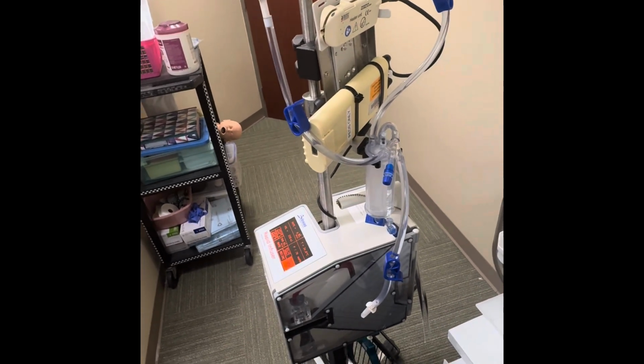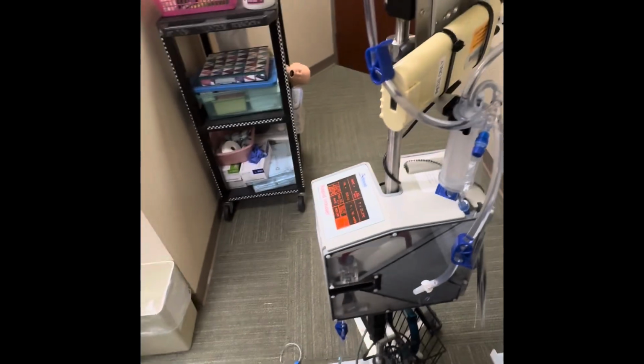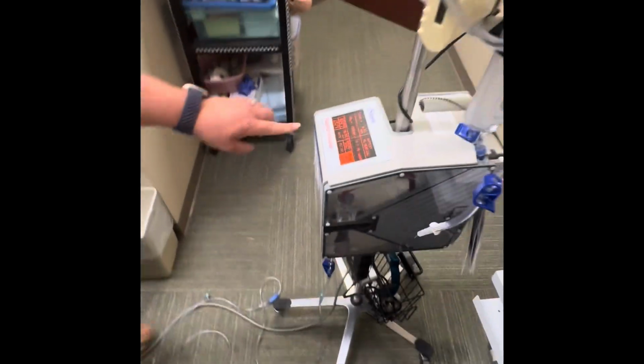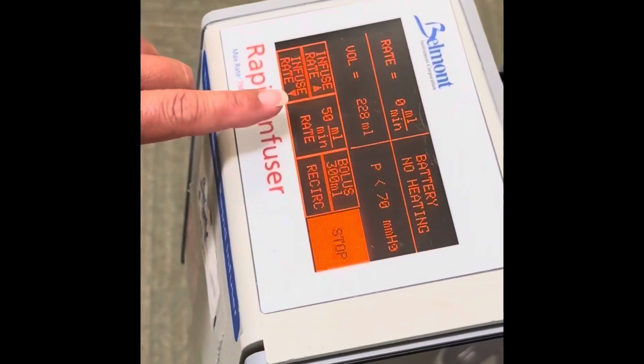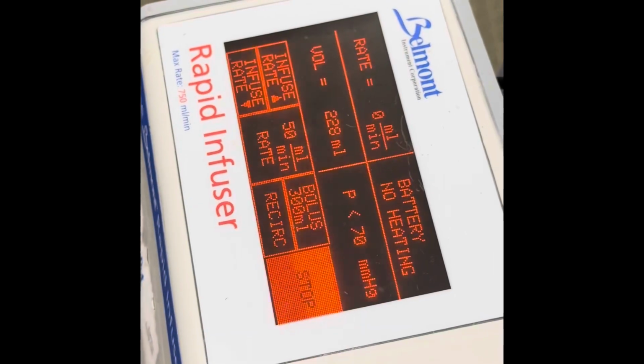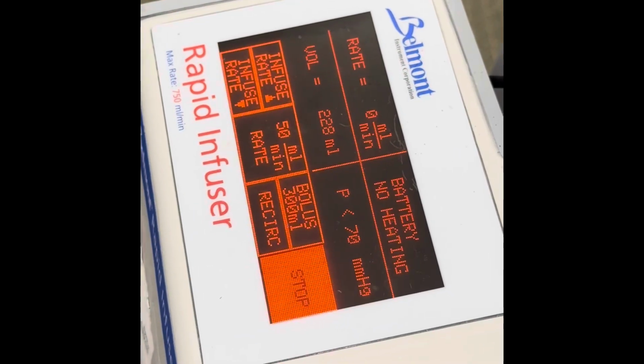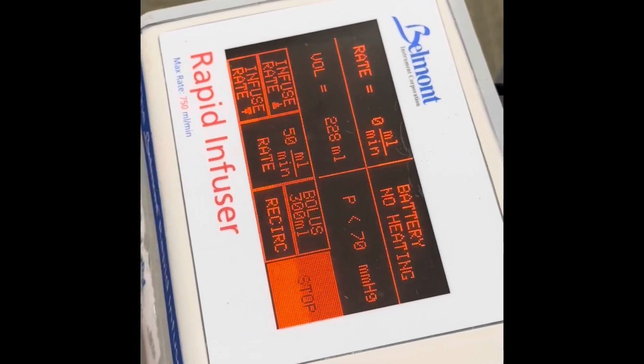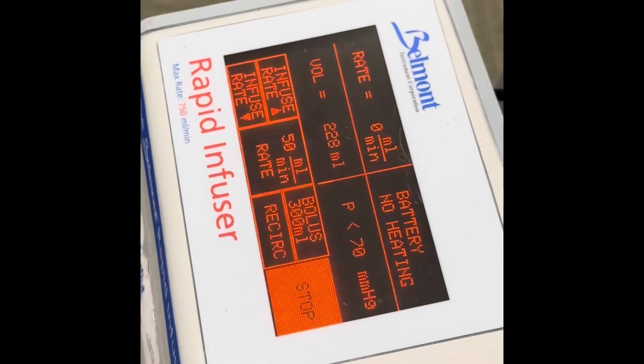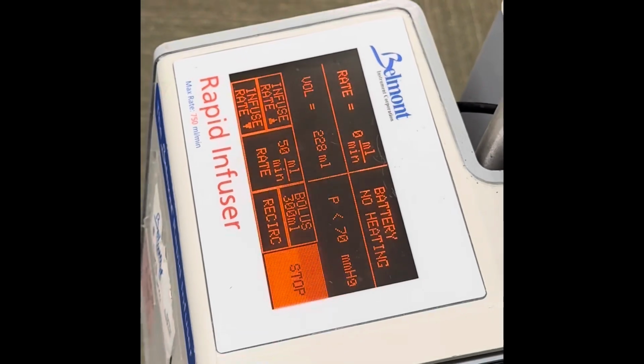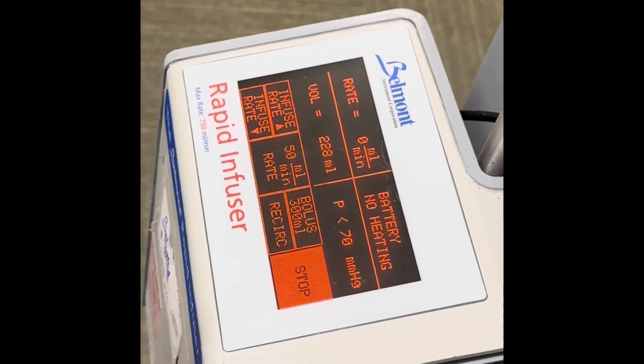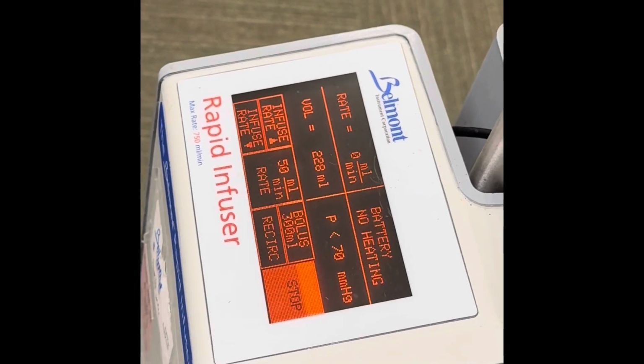Couple key points: keep the machine plugged in. If it's not plugged in, you'll see it drop from 500 mLs a minute to 50, and it tells you it's on battery with no heating, because it can't operate at that speed unless plugged in. We already talked about not using warm fluids on this machine because it has an automatic warmer when it's plugged in.